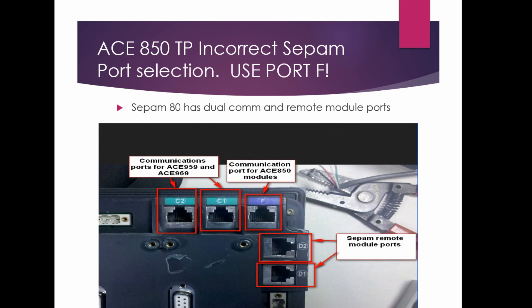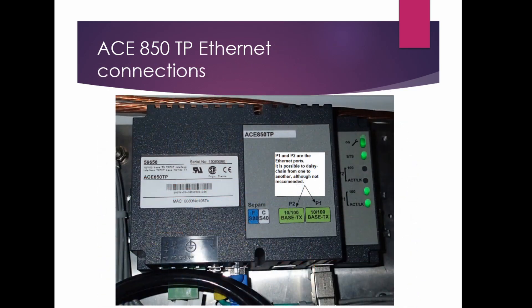When plugging in cables, make sure you're plugged into the right port on the base unit. Port F is where you plug in for your ACE850. C2 or C1 can be used for the 959 and 969 modules. D1 and D2 are used for modules such as the SyncCheck MCS025 or an MSA analog input/output module. Even though all the jacks look the same, they don't work the same.